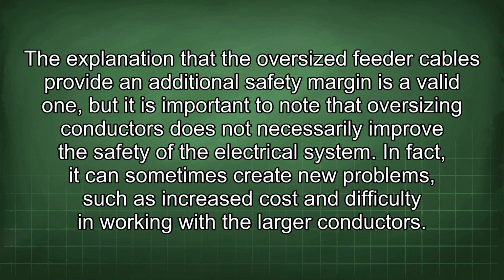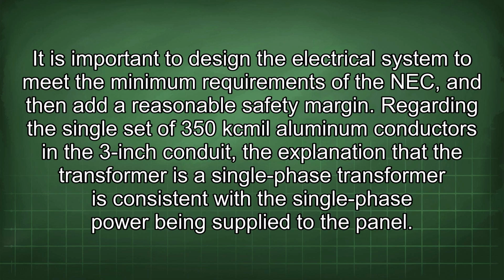The explanation that the oversized feeder cables provide an additional safety margin is a valid one, but it is important to note that oversizing conductors does not necessarily improve the safety of the electrical system. In fact, it can sometimes create new problems, such as increased cost and difficulty in working with the larger conductors. It is important to design the electrical system to meet the minimum requirements of the NEC and then add a reasonable safety margin.